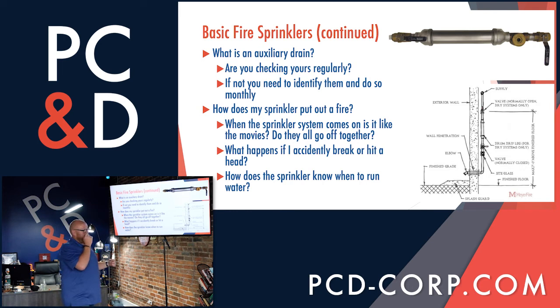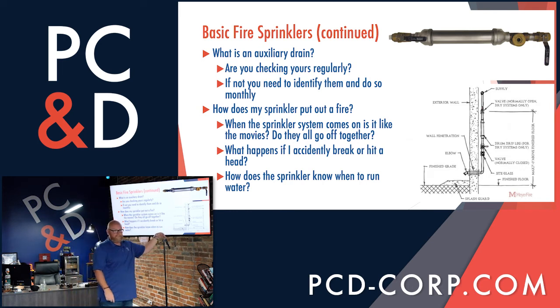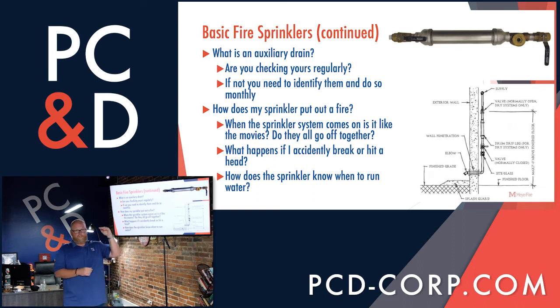So if you have a dry system in your attic and it's 0 outside and your attic is 12 degrees, that air pressure at 12 degrees is going to drop tremendously, as opposed to it being in the dead of summer at August, let's say. It's 95 outside, your attics are 120. The air pressure at 120 degrees versus the air pressure at 10 degrees, amazingly different. So the air in your dry systems is always going up and down. The goal of your air compressor is to try to stabilize it, okay?